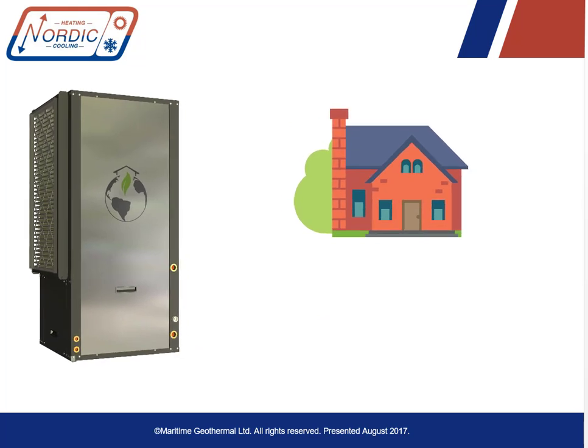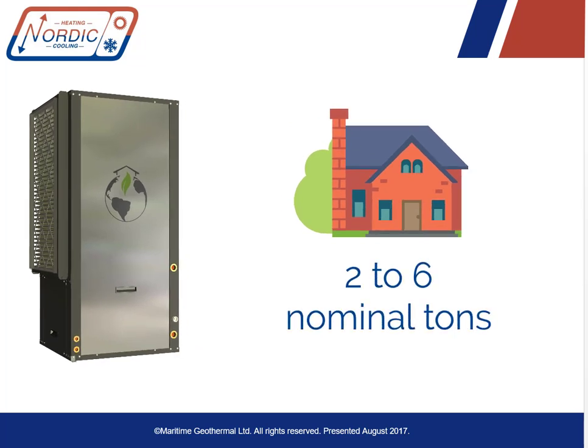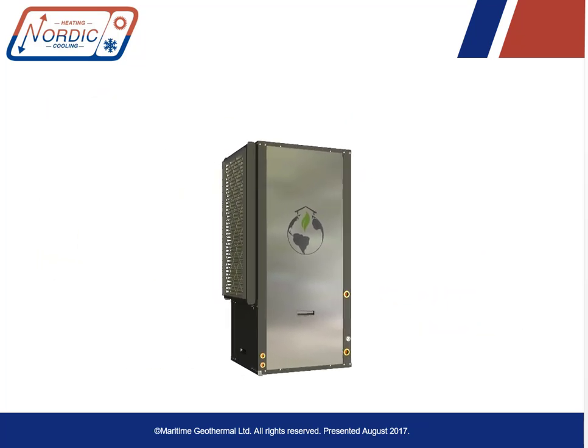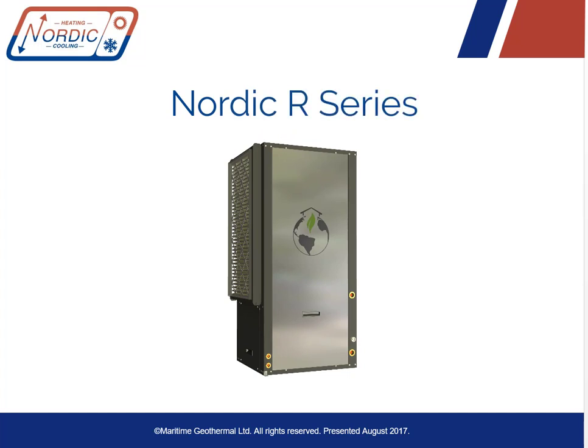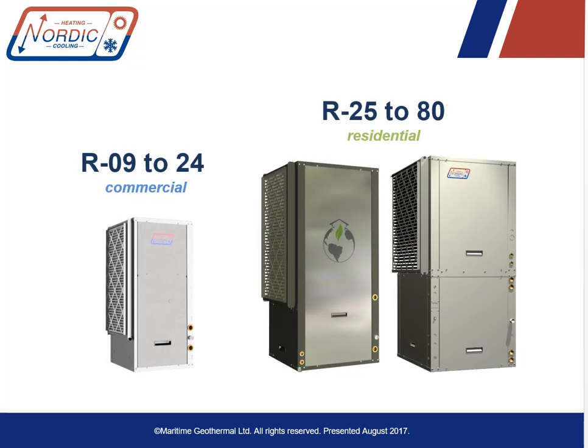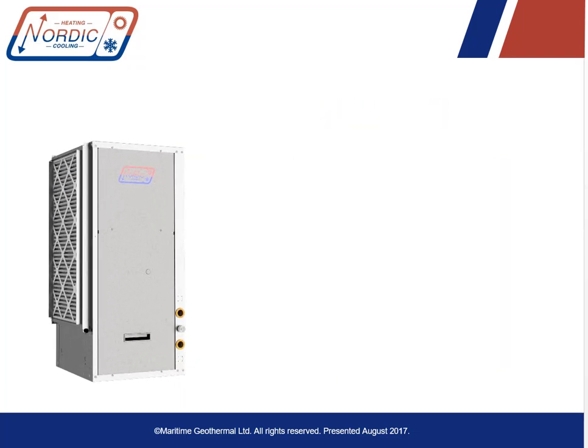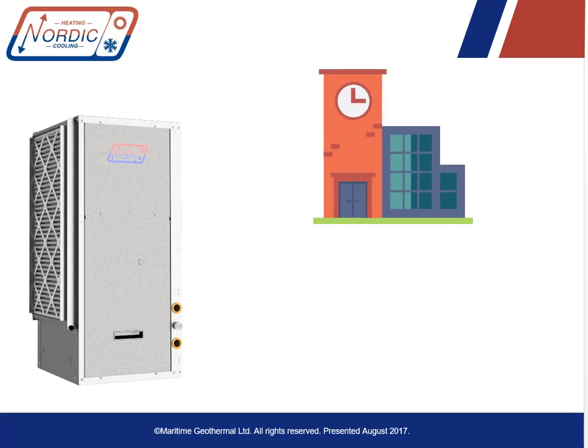So the unit size being 2 to 6 nominal tons refrigeration, or more commonly 3 to 6 tons in size. These residential units also tend to have the best premium sort of features, since they're often part of a geothermal system where the heat pump by itself might be a relatively small part of the investment. What I'm going to show you today is a newer series of water-to-air heat pumps. Although they will work for any type of location, these are aimed at the more cost-sensitive commercial market, so have cost-saving features that differ from the residential R Series.